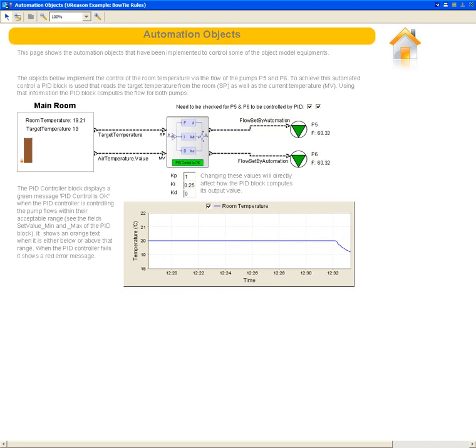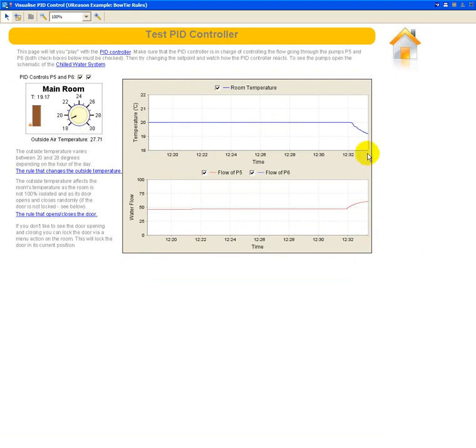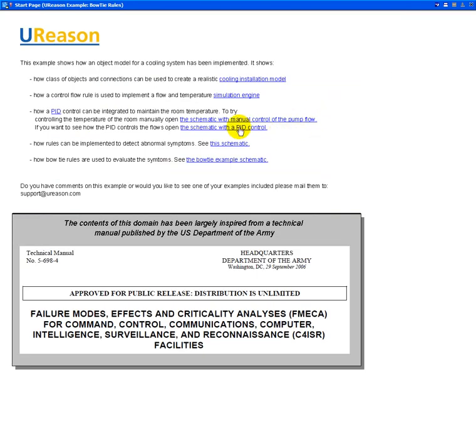So if I go back to the screen here, see that the PID has decided that the flow of the pump now should be around 60 or something like that. We can make the life of the PID a bit more complex by opening and closing the door here. The room is not completely isolated, so if I unlock the door of the room, there'll be more hot air coming inside the room. And in that case, of course, when the isolation of the room is not 100%, well, the PID will have to regulate that part of the temperature also. So that is to show you how the automated version of the simulation can be done.